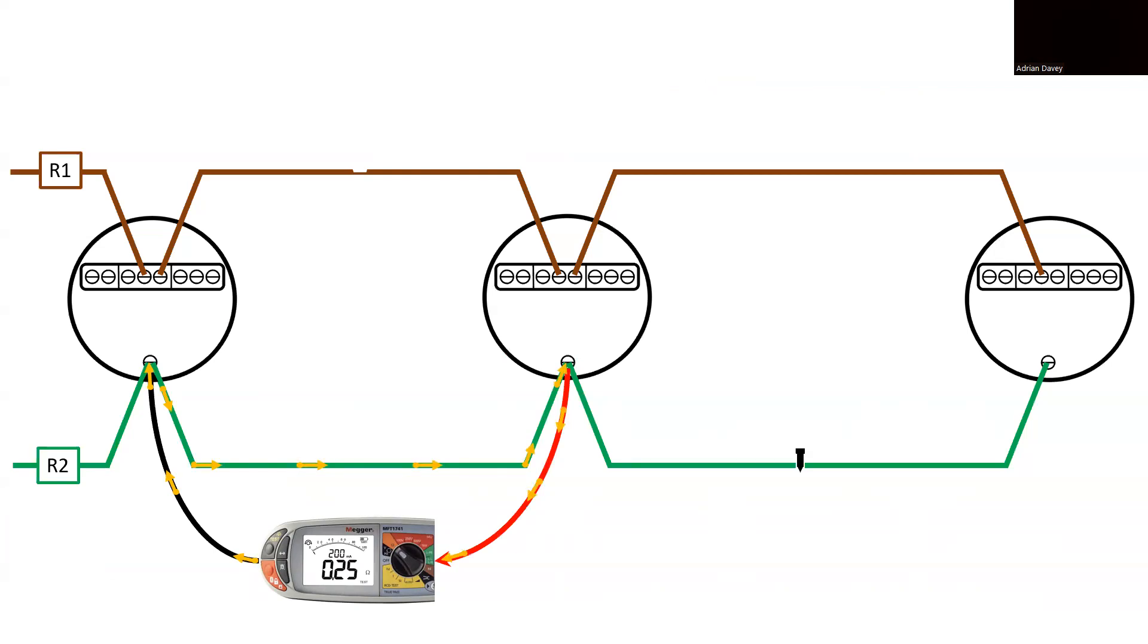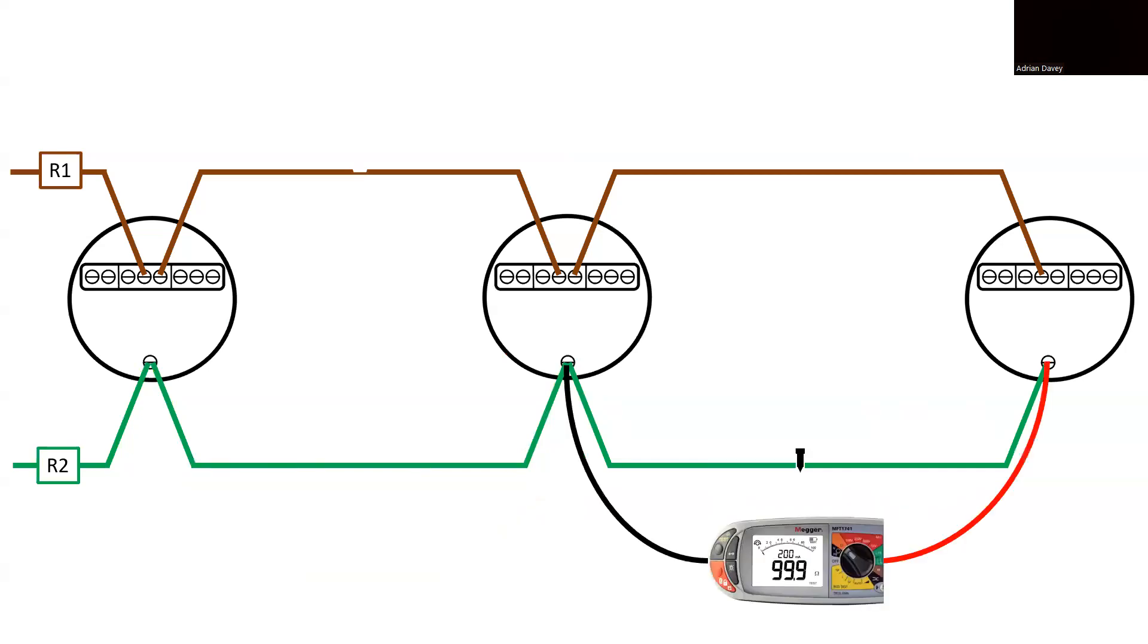Here, we measure 0.25 ohms, reinforcing that fault does not reside in this part of the circuit either. At last, we reach the final segment of the circuit, and because the circuit is broken, we lack a closed loop for electrons to travel on, resulting in an out-of-range reading of 99.9 ohms displayed on our MFT. This discovery allows us to pinpoint the location of the open circuit fault between two points.